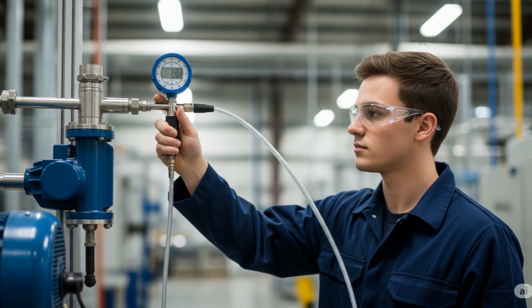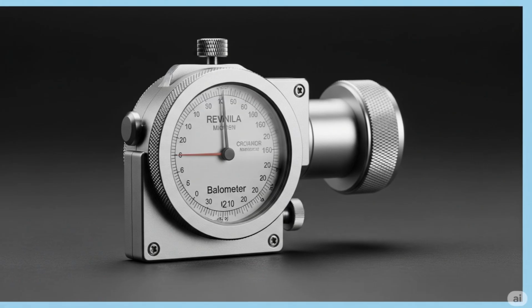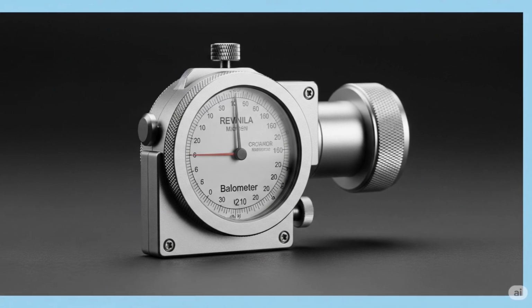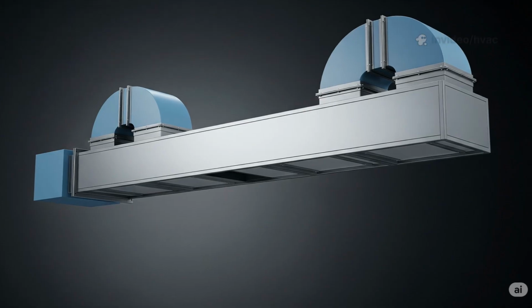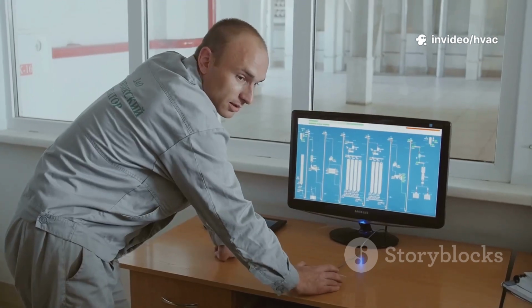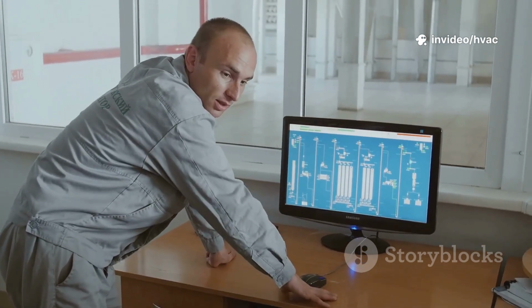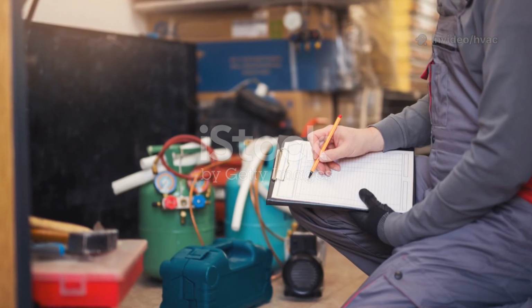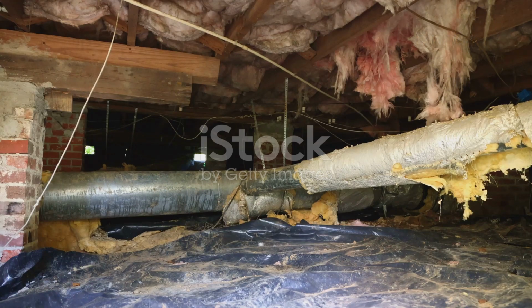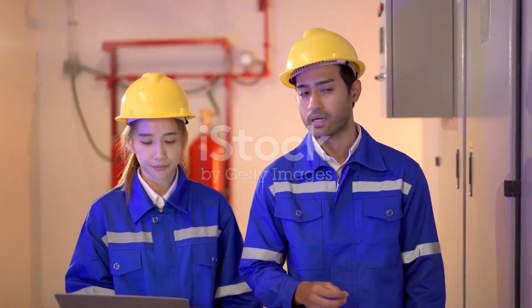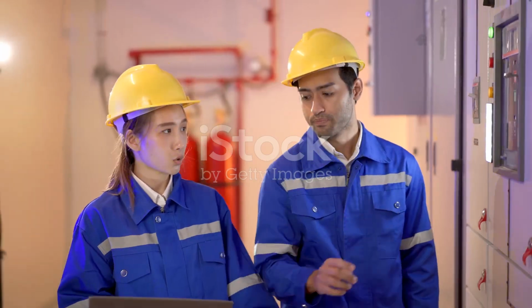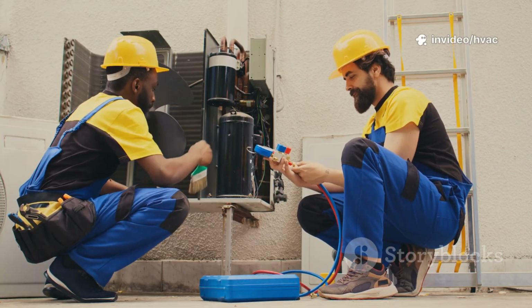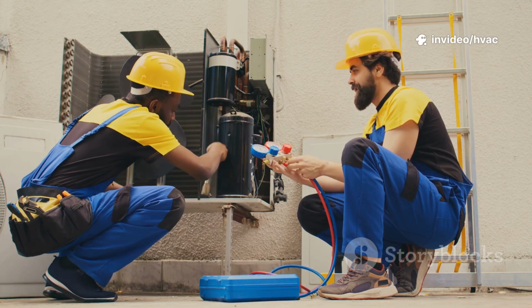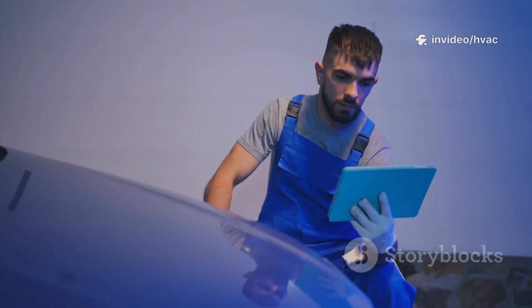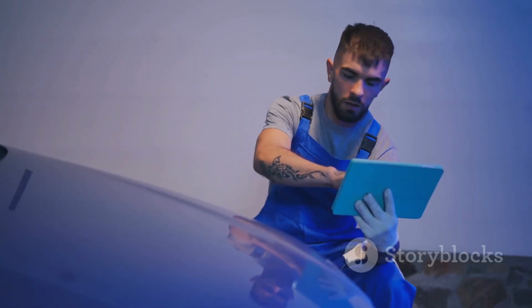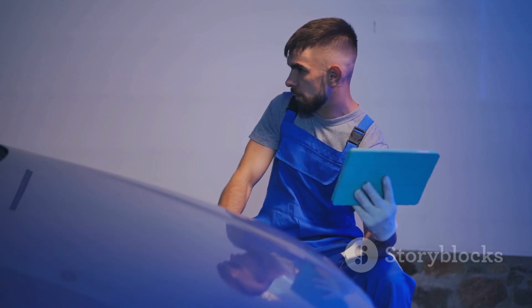After installation, always calibrate your AFMs on site. Compare readings with a trusted reference, like a pitot traverse, an anemometer, or an inline flow hood. Adjust zero offsets and scaling factors in the BMS. And make sure to recalibrate periodically, especially in dusty or corrosive environments. Always document your calibration results and keep certificates for future reference. Train your maintenance staff on proper calibration procedures to ensure ongoing accuracy, and set reminders for scheduled recalibrations to maintain system performance over time.